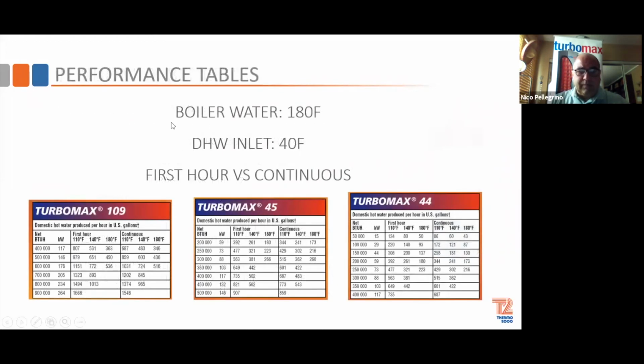So basically, a little bit of performance charts. The 109 can exchange roughly about 900,000 BTUs. So basically, this is your first hour here, this first column. These are your domestic temperatures. And this is your continuous. This is where we shine. You know, all day long, you give me 900,000 BTUs, you're going to get 1,546 gallons of water at 110 degrees Fahrenheit. So again, different sizes.